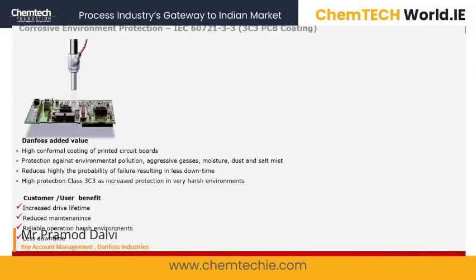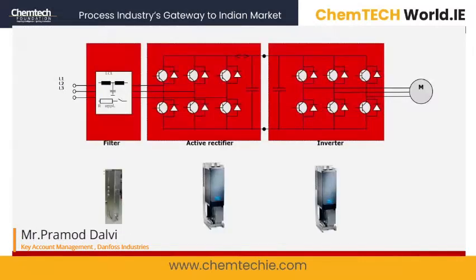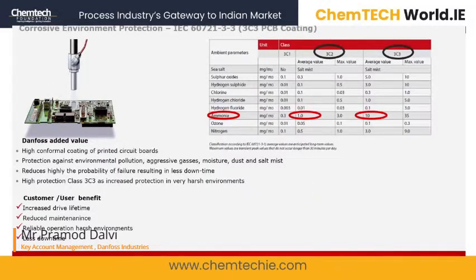I will just run through what is meant by harsh environment. The PCBs which are used in Danfoss drives are 3C3 coated. This is in compliance with IEC 60721-3-3, where it protects against environmental pollution, aggressive gases, moisture and dust. You can see in the red, for example, the difference between 3C2 coating and 3C3 coating is almost 10 times. So Danfoss drives have a built-in feature of 3C3 coating, and because of this, there is increased lifetime, reduced maintenance, and reliable operation in harsh environments.